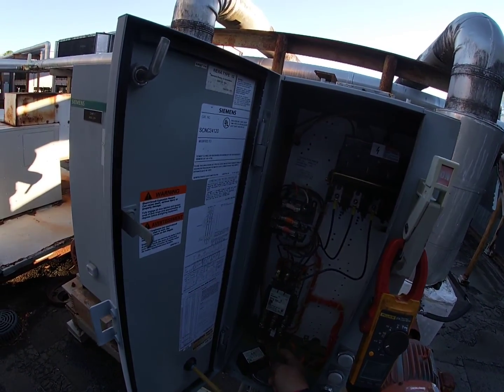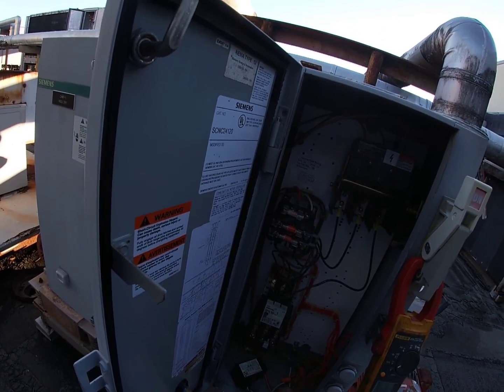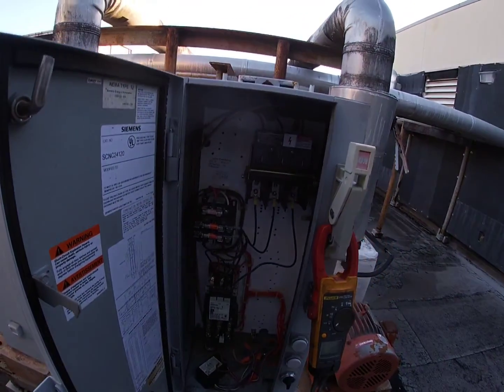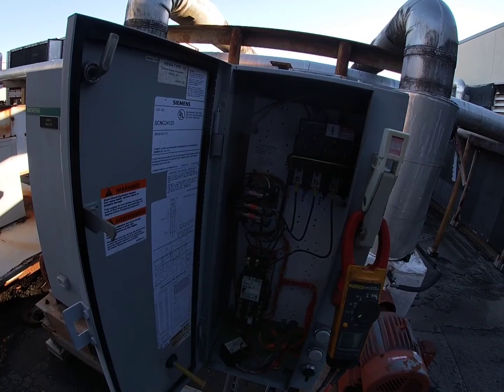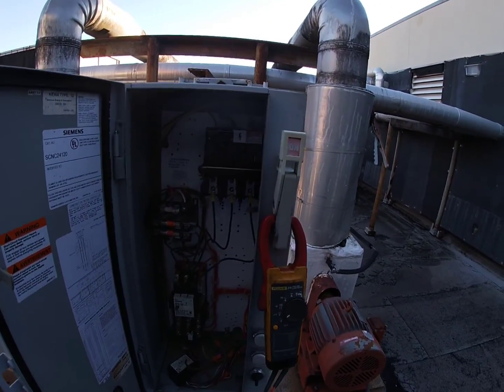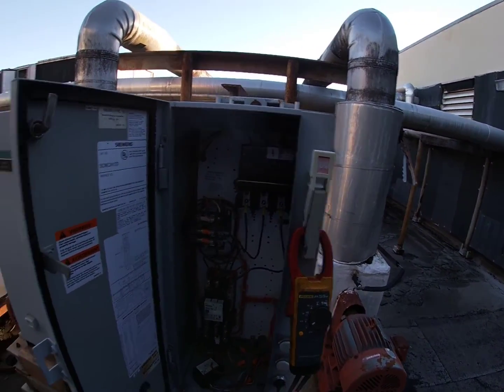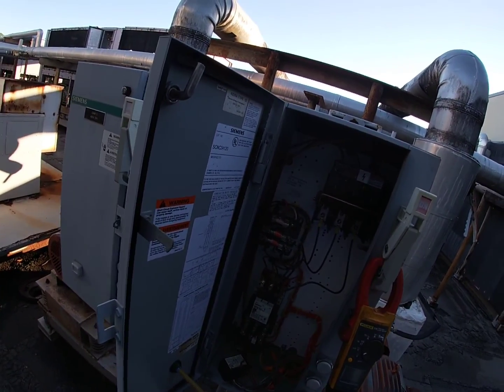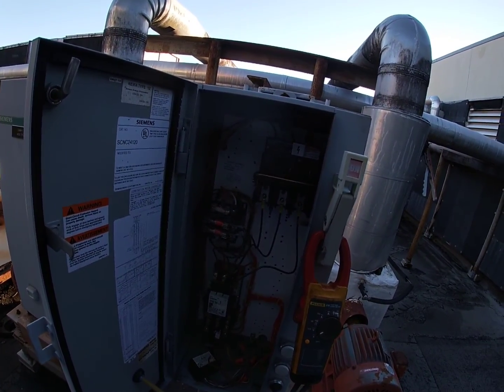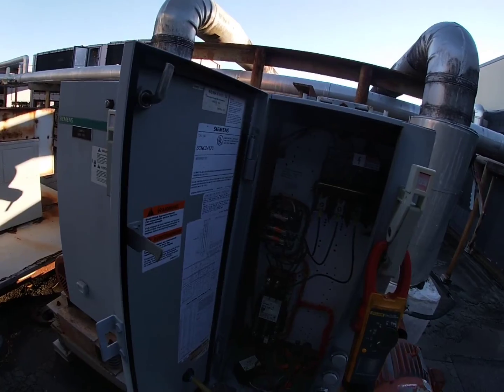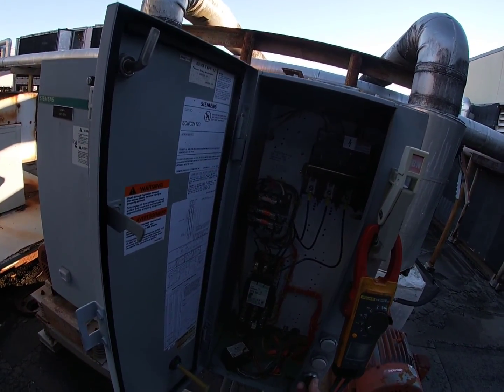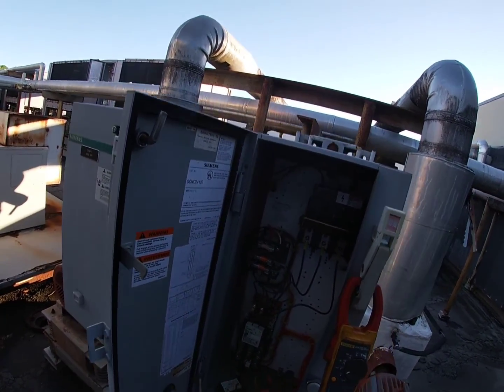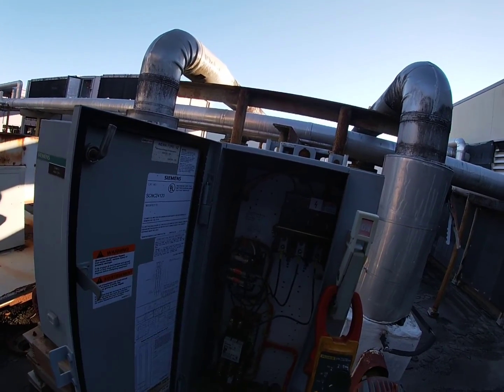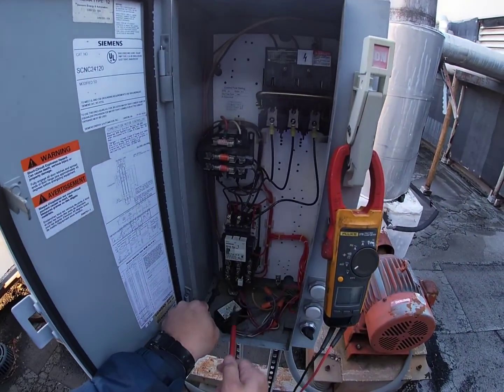So what happens is we're gonna hit this on. I already had the pump off. So earlier I just went ahead and hit this in the on position. It wasn't tripped, the starter wasn't tripped. I went ahead and put this in hand, and the HOA in hand. Pump made a weird noise, kind of like it was trying to start, almost sounded like it was losing a phase. And so I turned it off, pulled the wires off, turned it on, and let's see if we can get it to do the same thing here.